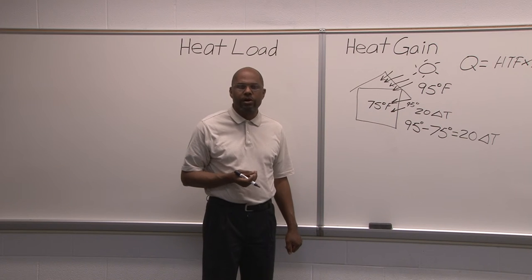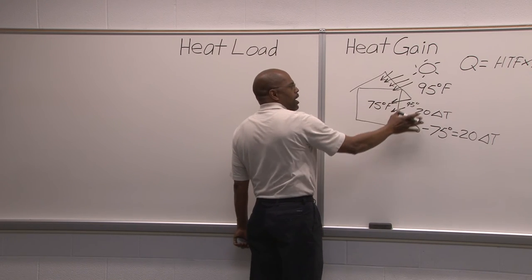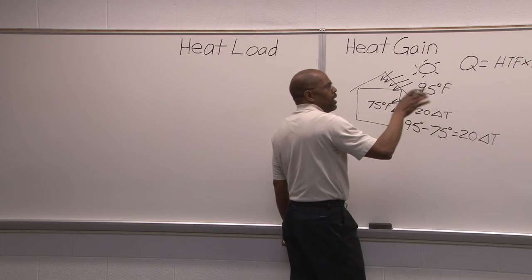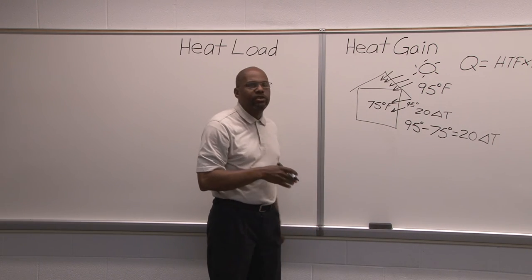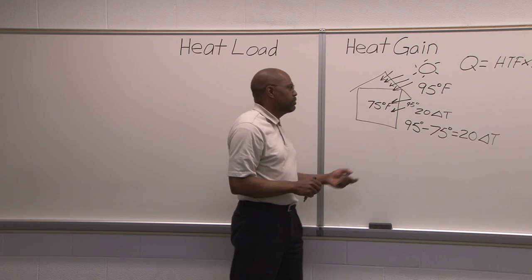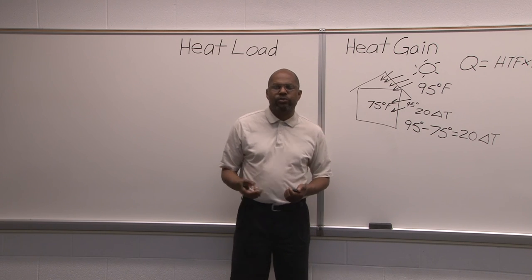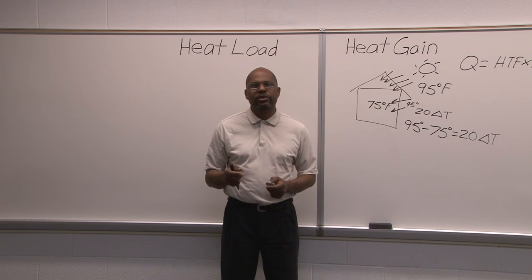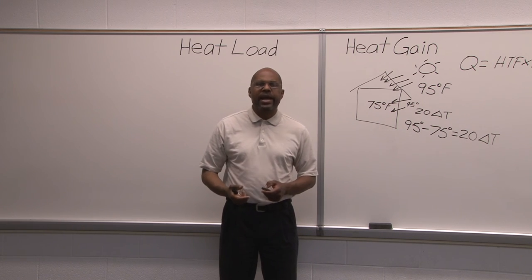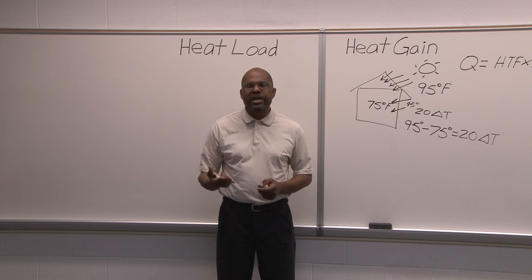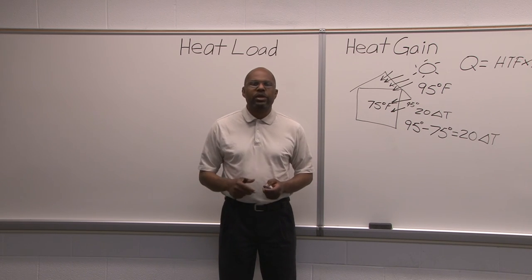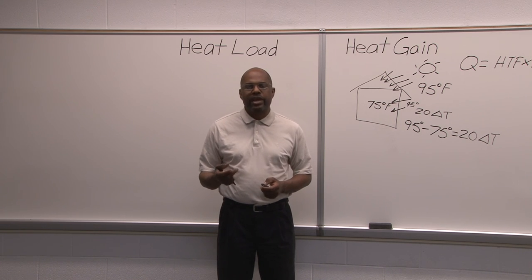A lot of times there's actually a heat loss in basements. So this is how we gain heat into a structure. Understanding heat transfer — by the heat transfer factor, the amount of material we have, and the temperature difference in the delta T — we can determine how we need to size equipment. When designing a house, we need to understand the type of materials we are using and their effect on impeding the flow of heat. The better the materials and the more insulation we use, the smaller the equipment we can actually have in the structure.